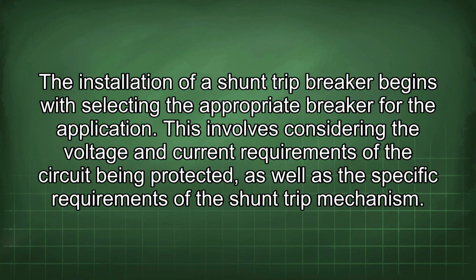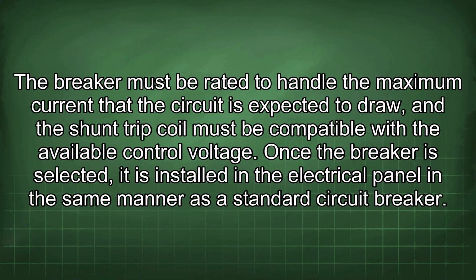The installation of a shunt trip breaker begins with selecting the appropriate breaker for the application. This involves considering the voltage and current requirements of the circuit being protected, as well as the specific requirements of the shunt trip mechanism. The breaker must be rated to handle the maximum current that the circuit is expected to draw, and the shunt trip coil must be compatible with the available control voltage. Once the breaker is selected, it is installed in the electrical panel in the same manner as a standard circuit breaker.